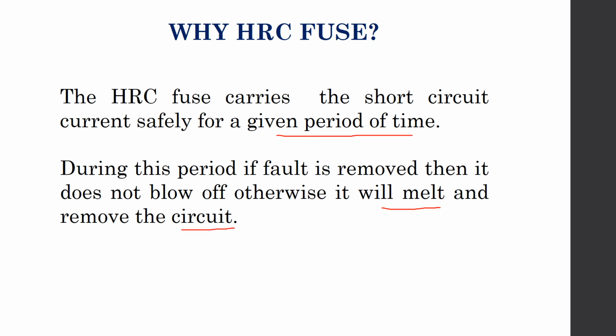Thus, we can see that HRC fuses carry the fault current for a given period of time. During this time, as said, if the fault is removed, the fuse wire will not melt. The fuse has inverse time characteristics, which means that if the fault current is high, then the rupture time or the melt time of the fuse wire will also be less, and if the fault current is not so high, then the rupture time can be long.